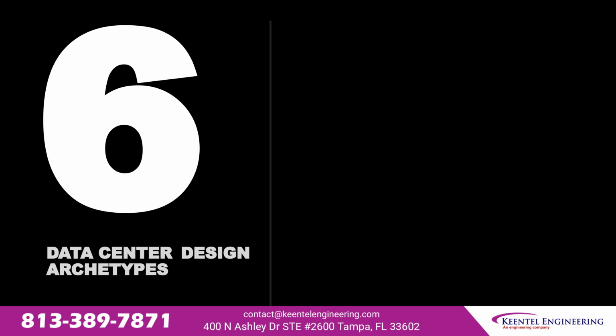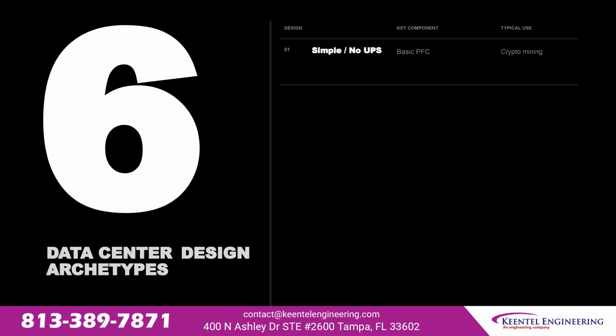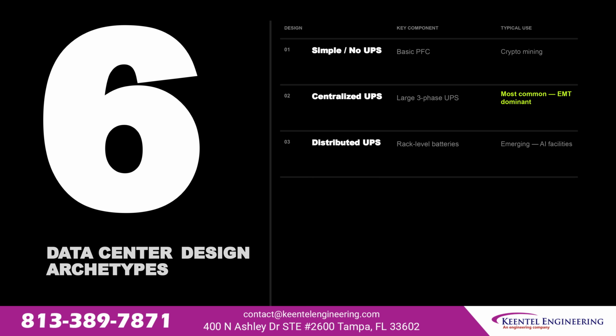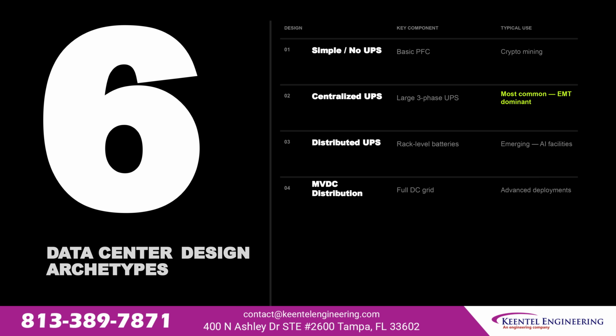6 data center design archetypes, each with a different EMT profile. 1. Simple, no UPS. Basic power factor correction, common in crypto mining. 2. Centralized UPS, large 3-phase UPS, the most common configuration and the most EMT dominant. 3. Distributed UPS, rack-level batteries, emerging in AI facilities. 4. MVDC distribution, a full DC grid behind the meter, advanced deployments.